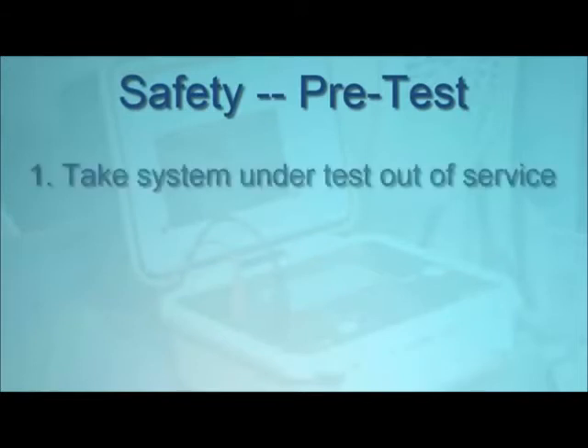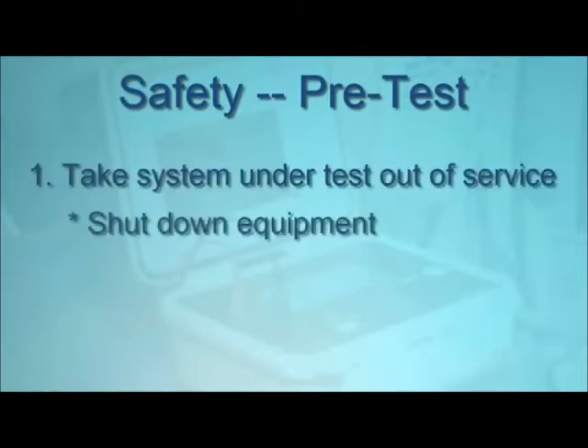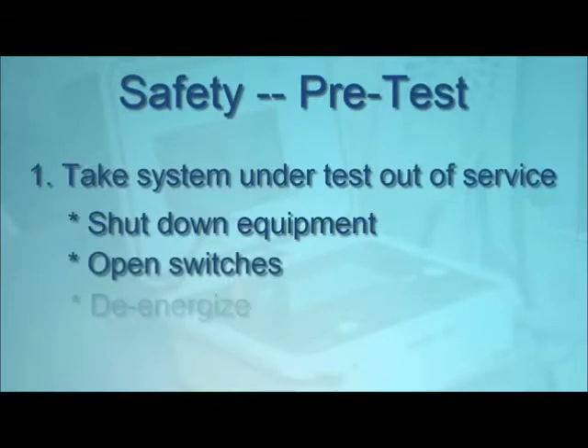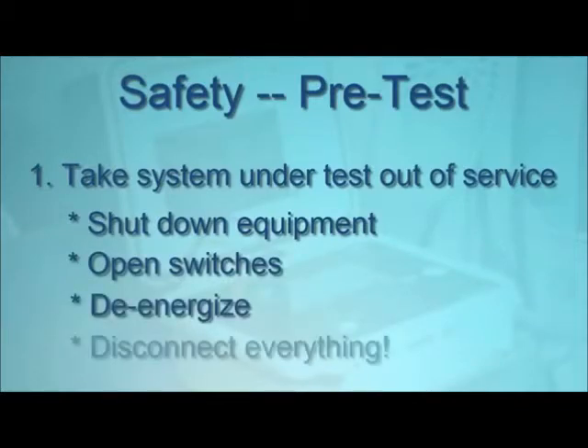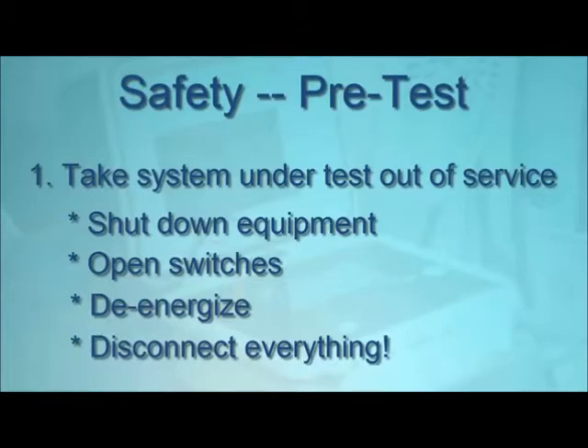First, take the equipment under test out of service. Shut down the apparatus, open all switches, and de-energize the unit. Disconnect from all equipment and circuits, including neutral and protective ground connections. Be sure to follow proper lockout-tagout procedures during this step.